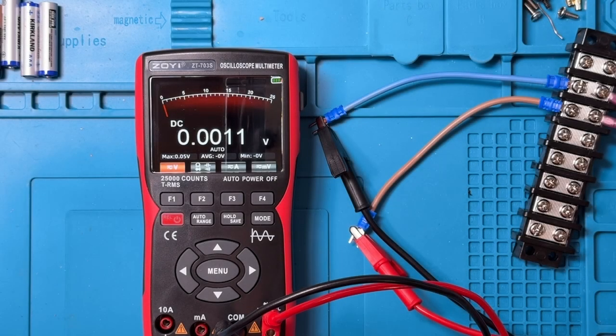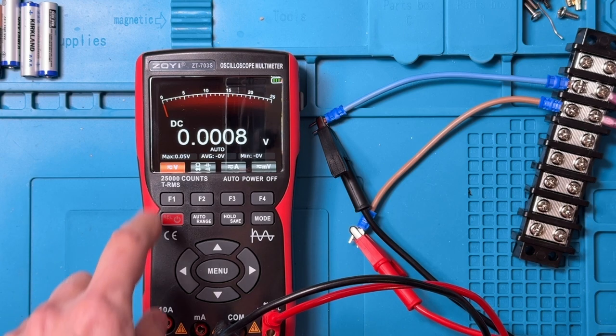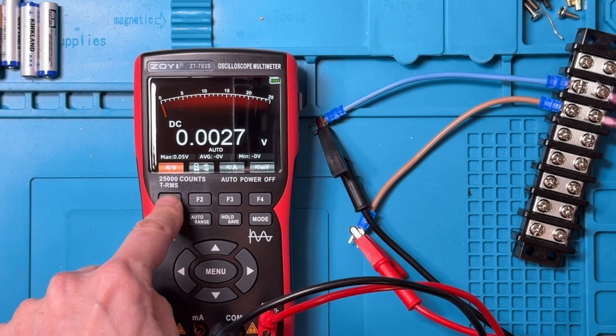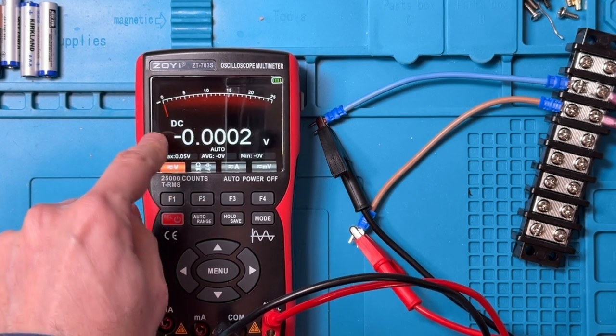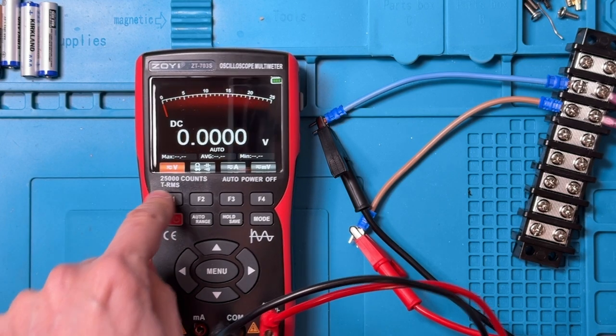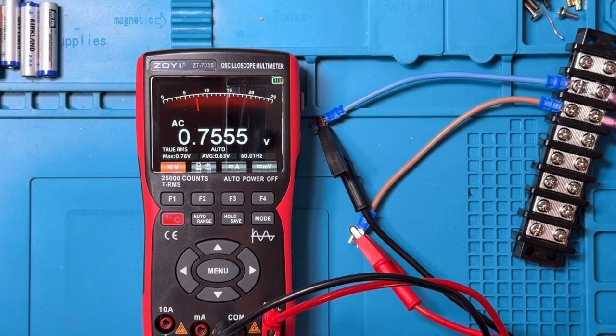Now we'll have a look at AC volts, and to switch into AC volts, we press the F1 button, and that'll switch us from DC volts where we are now. That switches us to AC volts. Now the power is not on yet, so we're seeing a little bit of ghost voltage. This unit doesn't have low impedance mode.